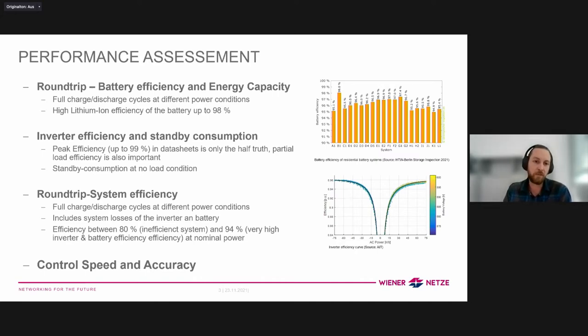What we can test regarding the performance of such systems: the first thing is, of course, the efficiency, the battery efficiency and the energy capacity. We do this by applying multiple full charge and discharge cycles at different power levels. Our experience from testing many different battery systems and sizes is that lithium ion efficiency can be quite high, usually between 90 and up to 98%. This is only on the DC side.